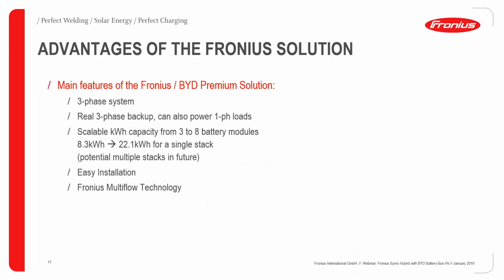Some of the main features and advantages of the Fronius solution with the BYD Premium: it's a real 3-phase system, can produce a real 3-phase backup, and obviously can power single-phase loads as well. The scalability goes from 3 to 8 battery modules of the HVM, 8.3 up to 22.1 kilowatt hours for a single stack, with potential for multiple stacks in future. We're fairly confident with that, but it hasn't been 100% confirmed yet. Nice easy installation, using the MULTIFLOW technology for your charging.